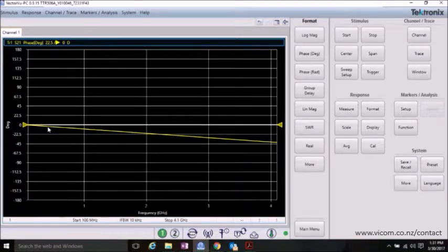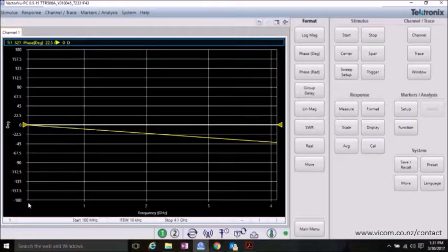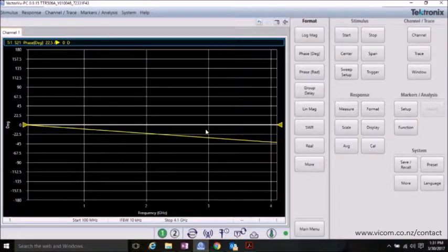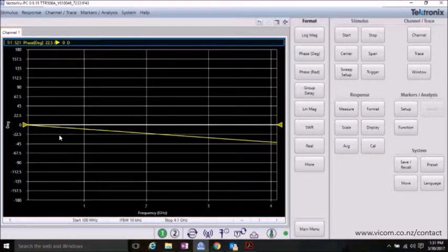Note that the phase response of S21 without any DUT is linear but not completely flat at zero. We need to add a port extension to make this line zero.